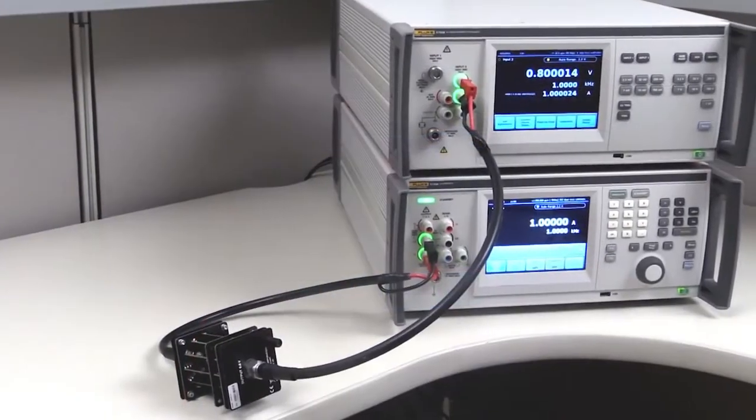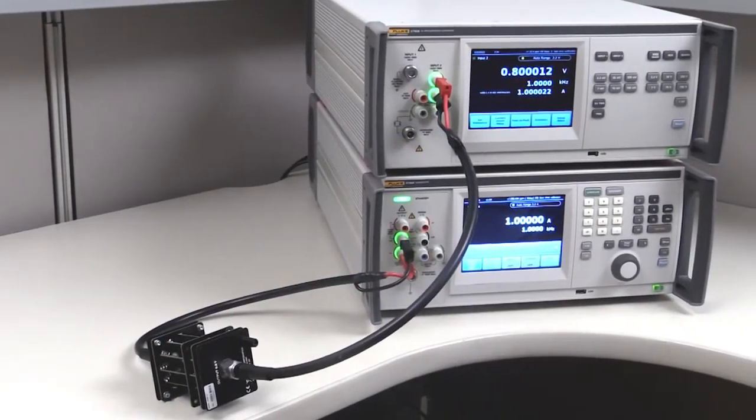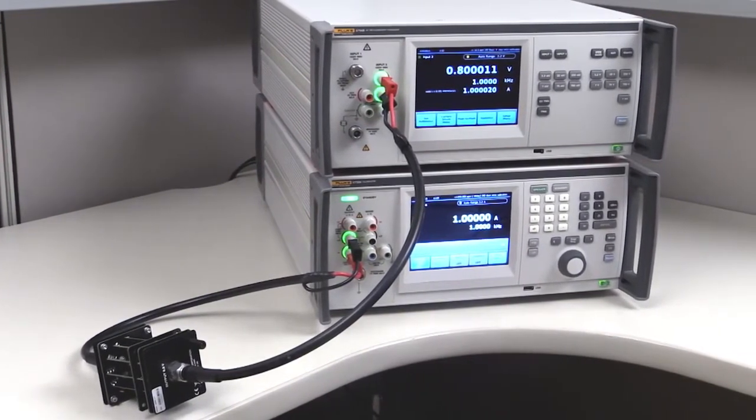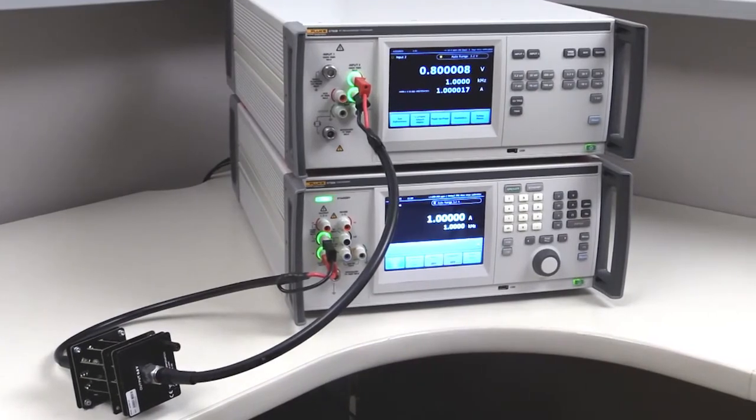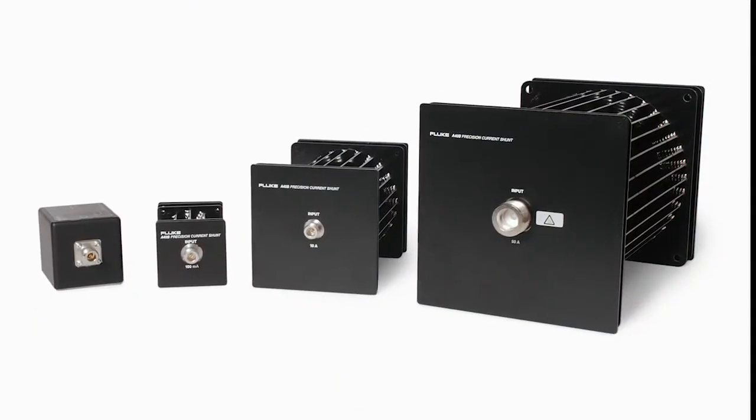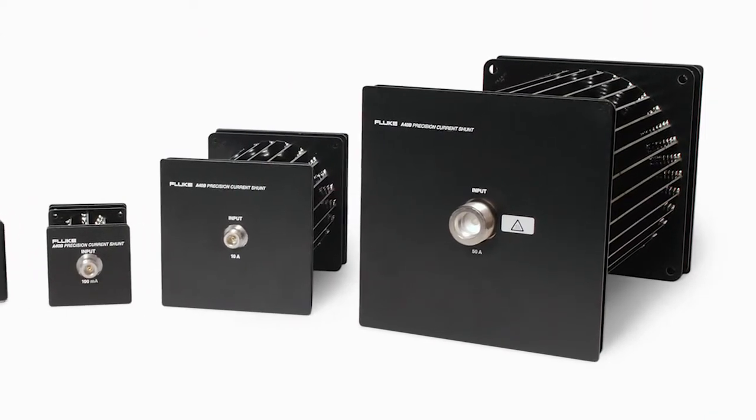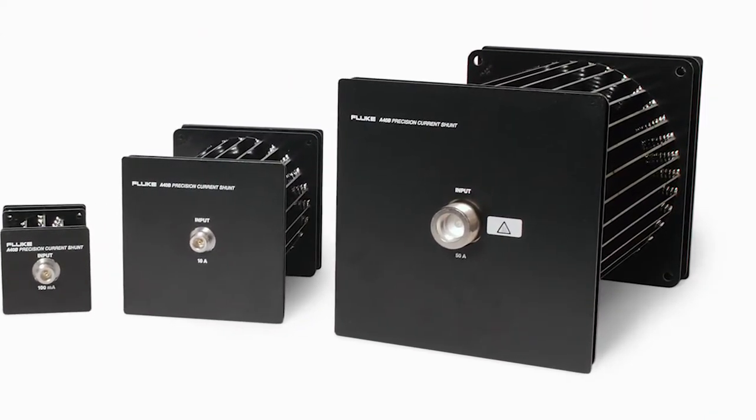The second major improvement is the 5790B's ability to make direct, absolute, or relative current measurements with current shunts without needing to make any calculations. The 5790B is optimized for use with the Fluke A40B current shunts up to 100 amps to make absolute and relative measurements.